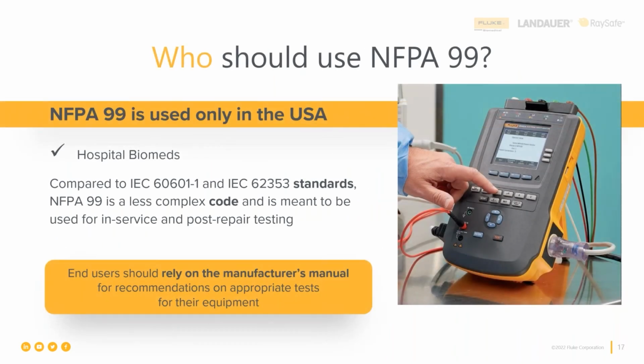So who should use NFPA 99? NFPA 99 is only in the United States, shouldn't be used outside the US, and it's intended for hospital biomeds and has fewer tests and less often. Because why? As I said before, the NFPA is about fire protection and reducing the risk of fire from electrical sources. So if we use 62353, we more than satisfy the NFPA 99.